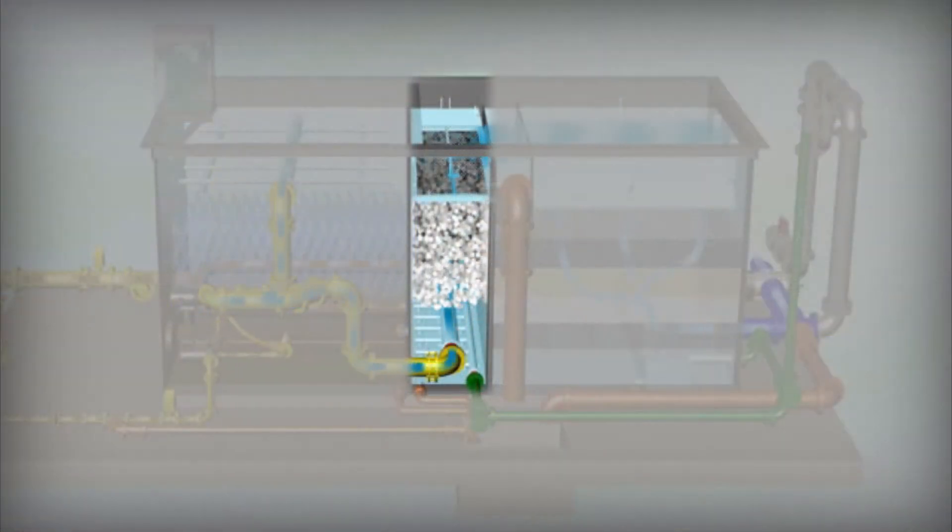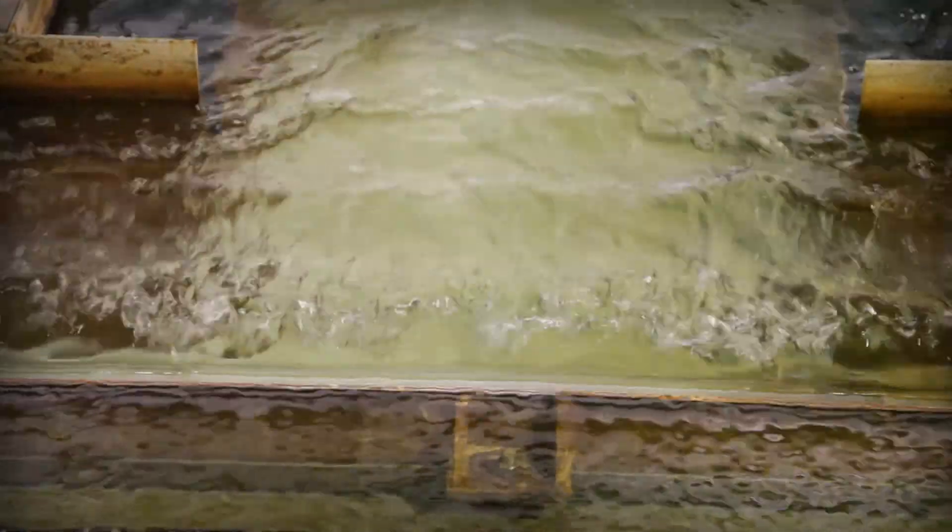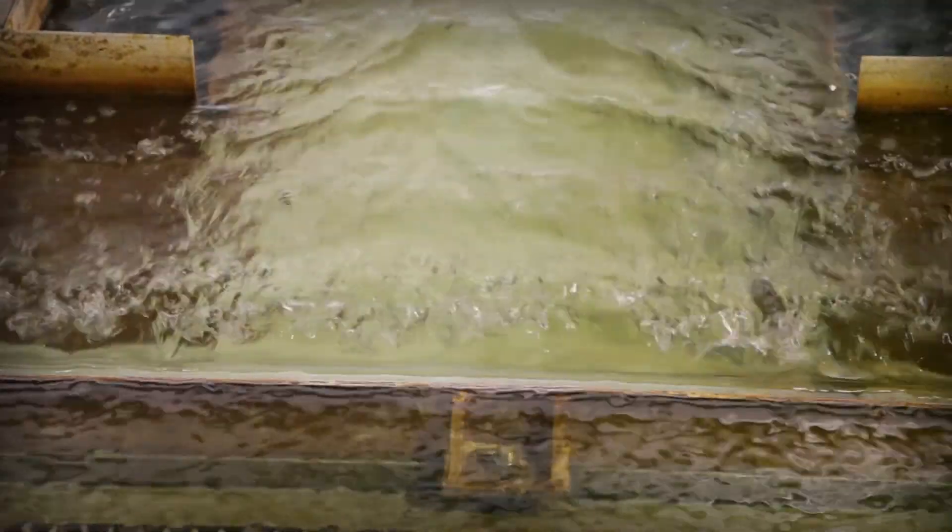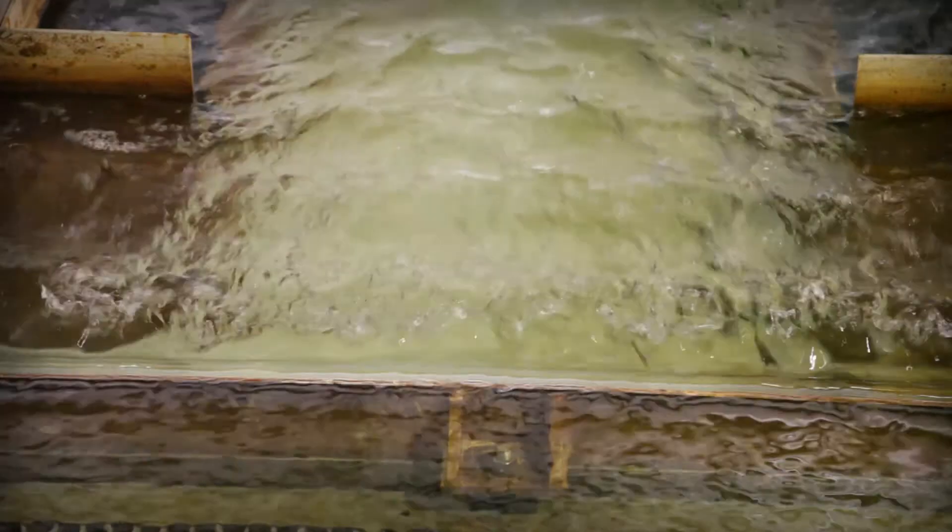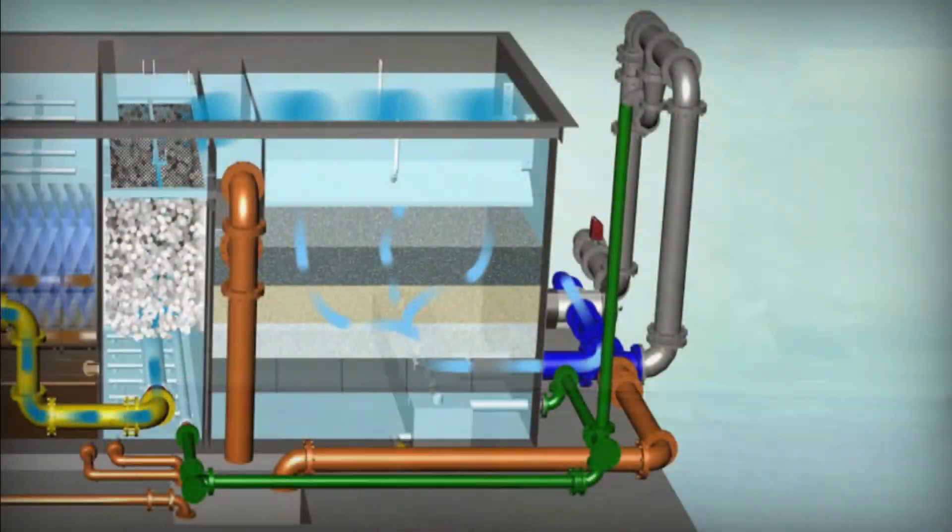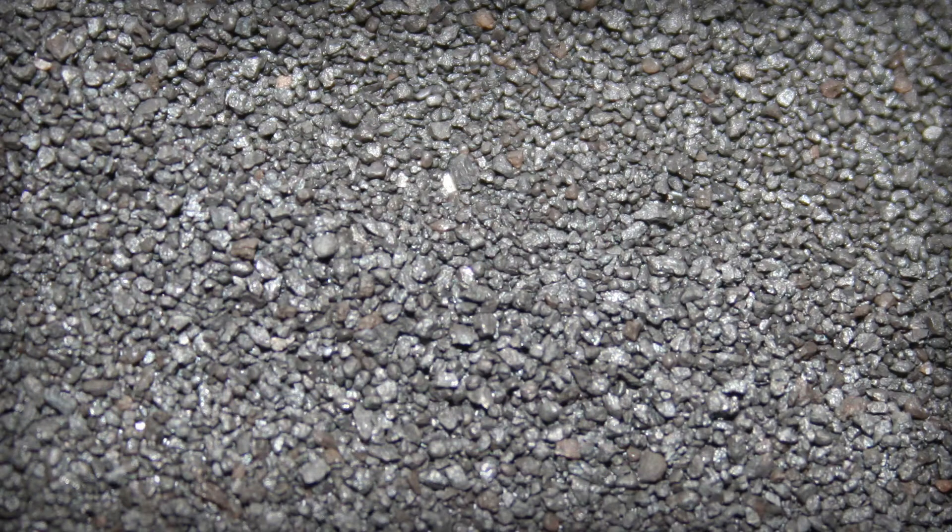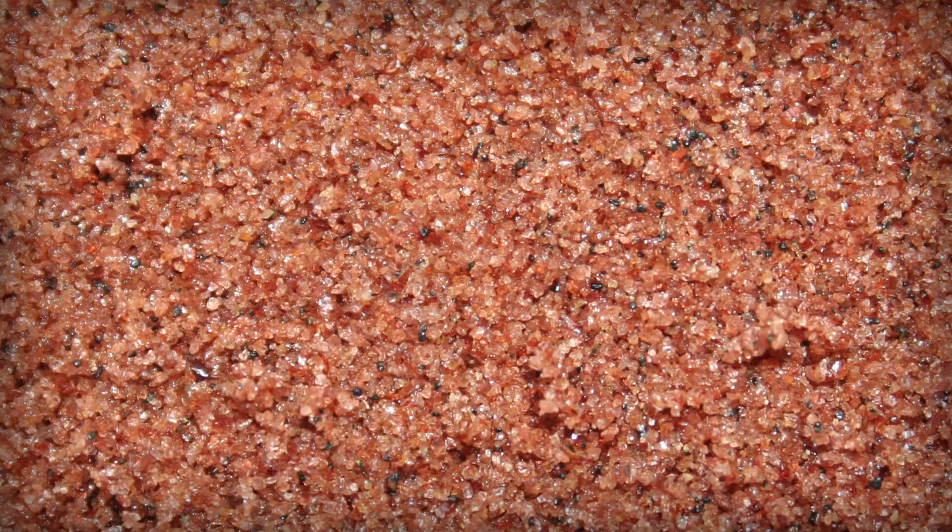The third stage in the Trident HS system is the mixed media filter, which polishes the effluent from the adsorption clarifier. This is the last physical removal stage of the system. Clarified water flows downward through specially selected filtration media consisting of anthracite, sand, and high density garnet.